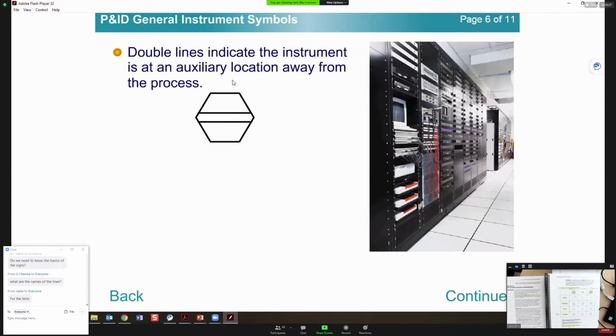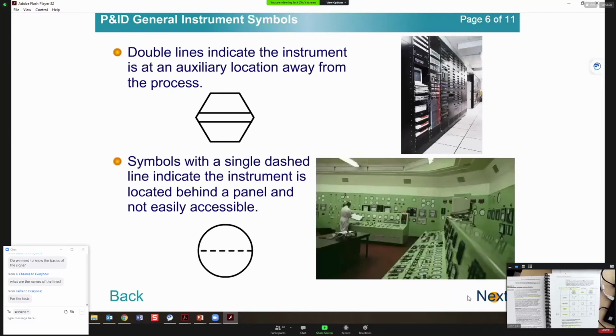If they have double lines inside, that means this instrument is located at an auxiliary location away from the process. So they could be mounted inside a big control panel or wherever. If you have a dotted line inside, or they call it a dashed line, that means this instrument or equipment is mounted behind the panel, not easily accessible. So those are the symbols and the meanings for those.